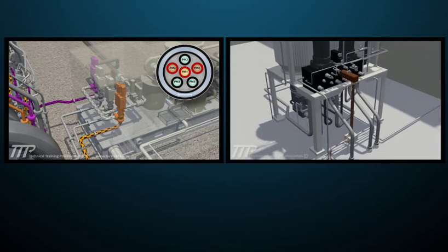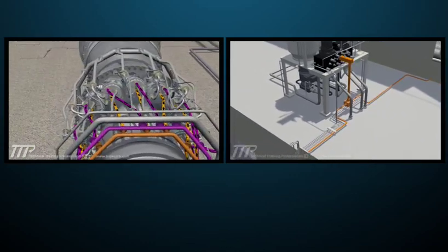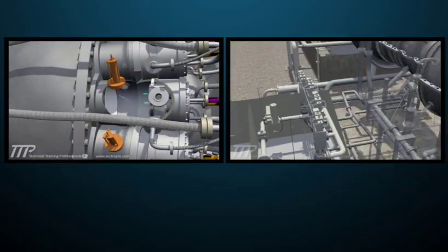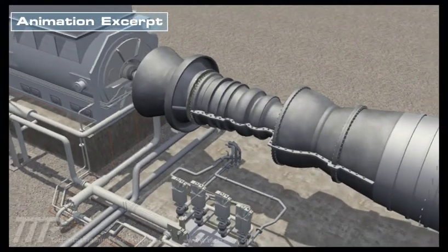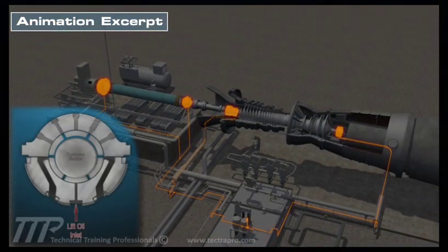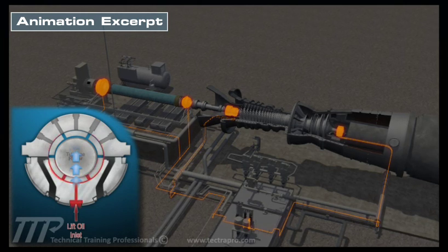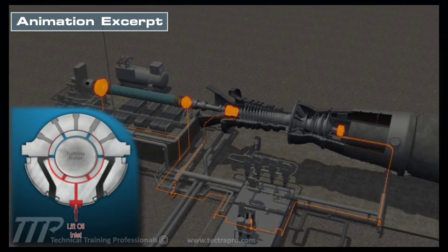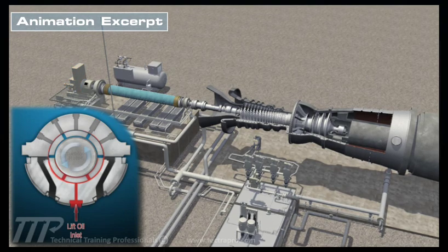By first showing location, use, and design of a component, the person performing the maintenance procedure gets a clear background of component function and integration with system operation. Lift oil is piped to the dead bottom center of all four bearings to provide a film of oil and lift the entire rotor. With a wedge of oil in between the shaft and bearings, the turning gear can turn the shaft.